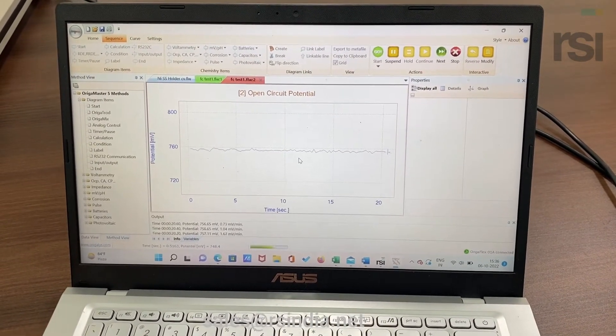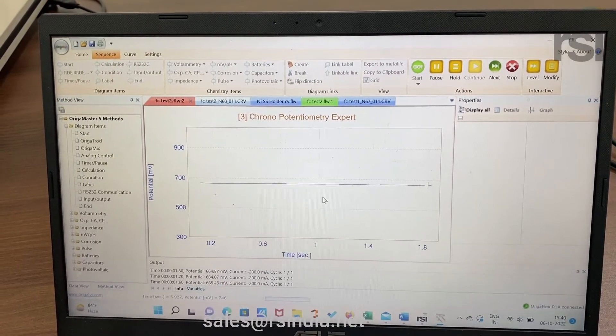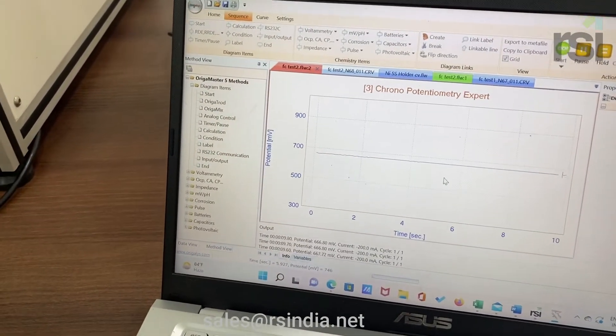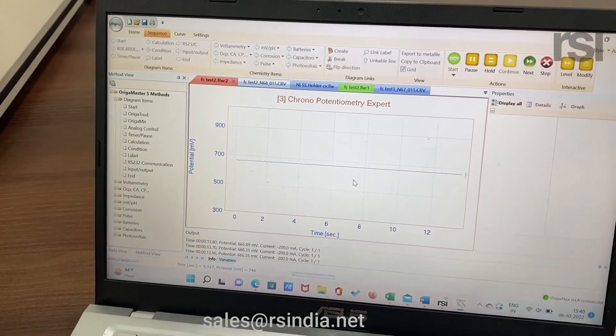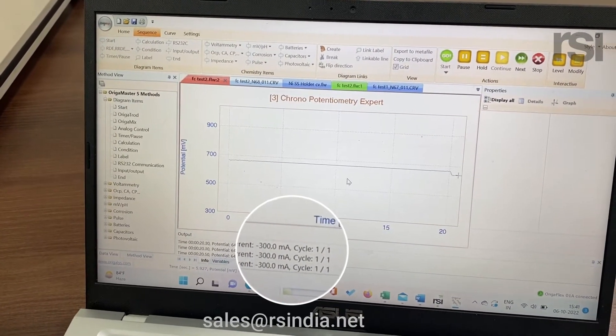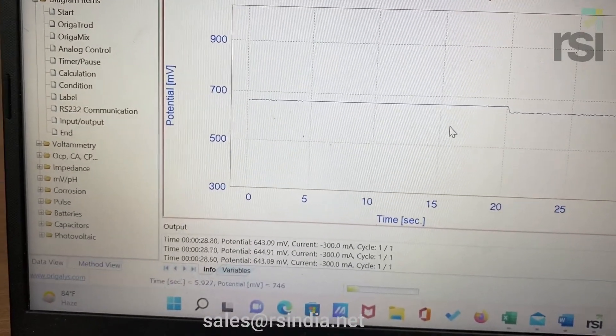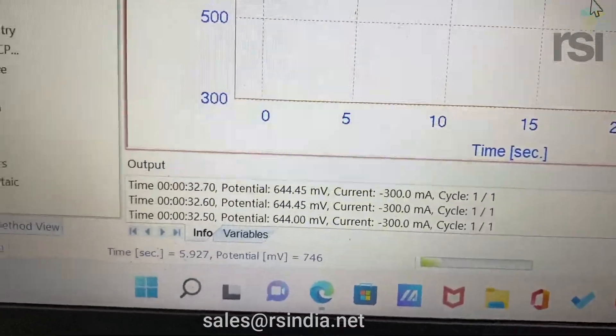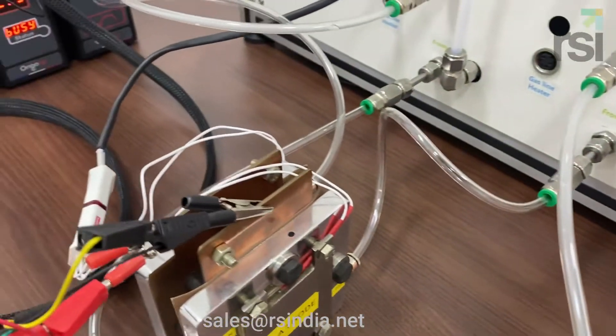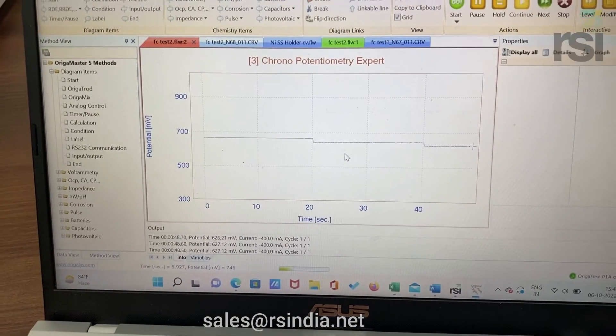After 20 seconds, you can see the instrument will start — 760 mV — and now we started drawing the current. It is drawing 200 mA current for 20 seconds. After 20 seconds, it moved to 300 mA current, and then you can see the voltage dipped a bit. Now it is drawing 400 mA current. You can see the voltage is still going down.